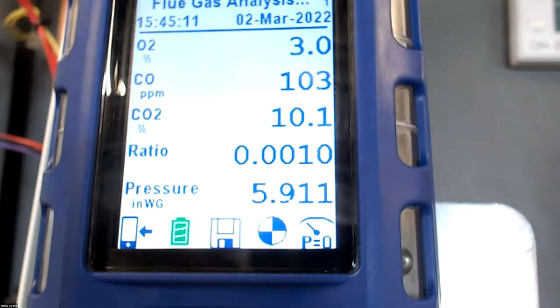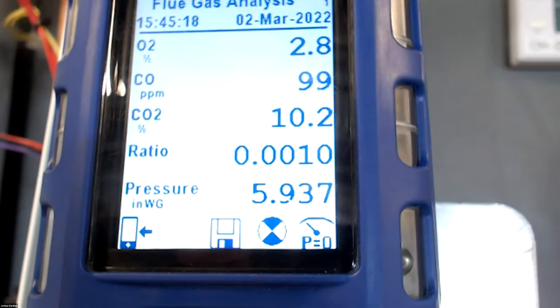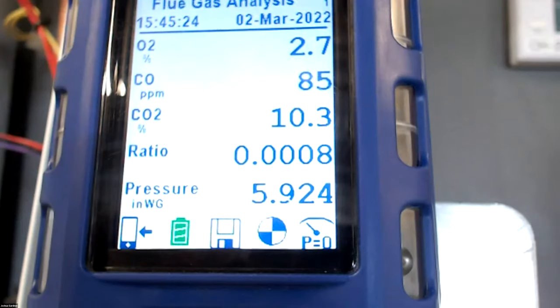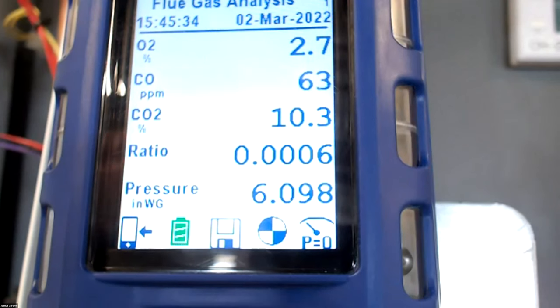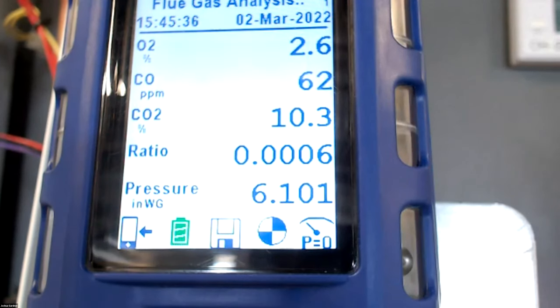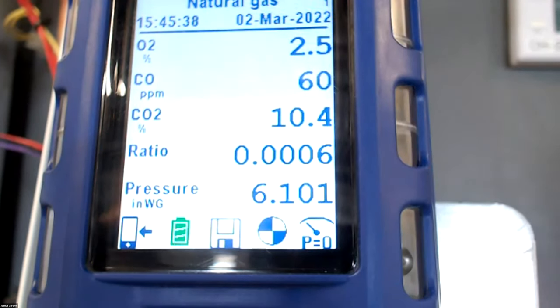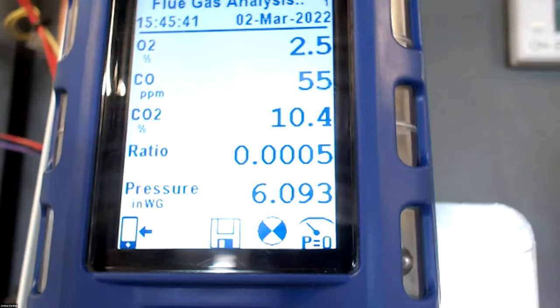When we get in the low fire, we just need to be on the CO2 between 9 and 10, and the O2 between 3 and 4.5. And we'll bring it down to 1%. There we're at low fire. We'll give this a few minutes to plane out. Our CO is still at 60, everything's dropping. It'll take a few minutes.